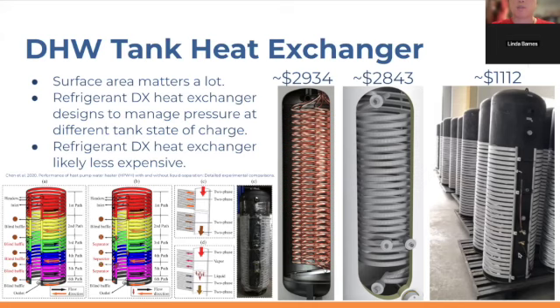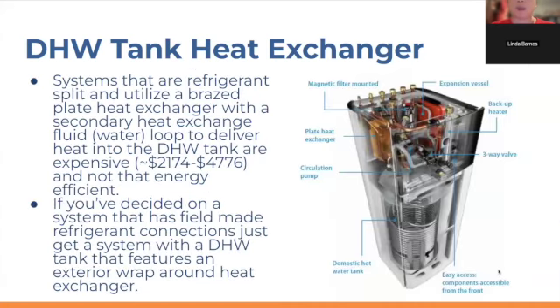Because before this game-changer heat exchanger design, what happened in the past is that manufacturers, even in a refrigerant split system, would pipe the refrigerant into a brazed plate heat exchanger, then have a circulation pump and a closed loop of water going between the brazed plate heat exchanger and a heat exchanger internal to the tank. This convoluted heat exchanger design is very expensive. If you think the $2,800 tank is expensive, tanks with this design sometimes go as high as 4,000, almost $5,000.